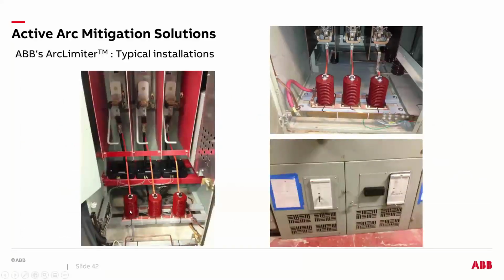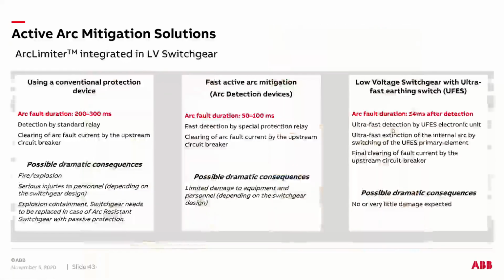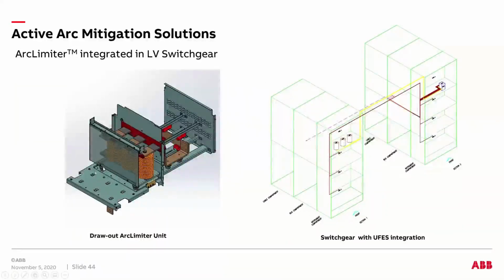Some of the typical installations, right? This is actually a retrofit installation where we have installed a UFES with the CTs for the REA, CT input for the REA, and it's a similar picture on the other one. And I would like to wrap it up by showing the arc limiter being integrated in our low voltage switchgear, right? Here we show a withdrawable unit that can be integrated in our low voltage MNS switchgear. That's a unique feature where, for non-arc resistant equipment, we can integrate the UFES elements within the switchgear itself, right? So for the main time, we can connect it in such a way.